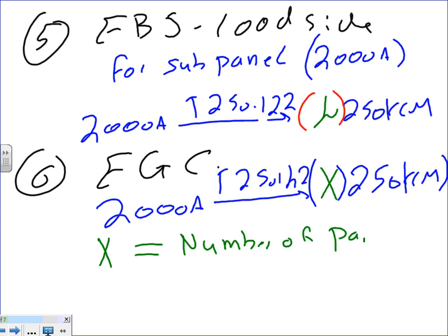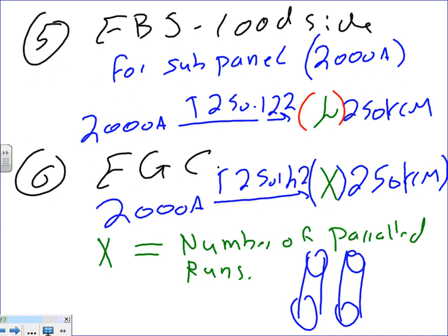I'm going to say x equals the number of paralleled runs. Now that's when you have parallel runs. Suppose that I parallel 3 runs for this feeder, 1, 2, 3. Then x will be 3. Suppose I parallel 10, x will be 10. Any question, guys? Why did I put x? How many of them do I need? 1 for every parallel set. If you only have 1 set, then you only talk about 1.